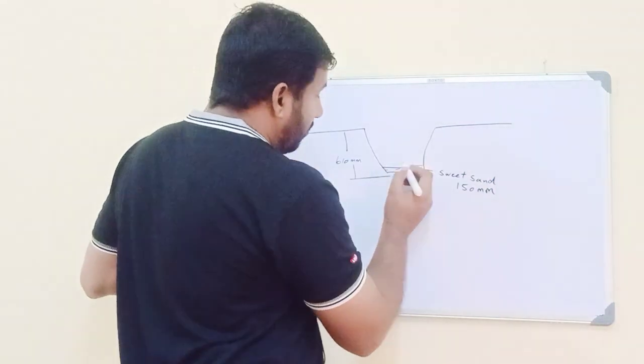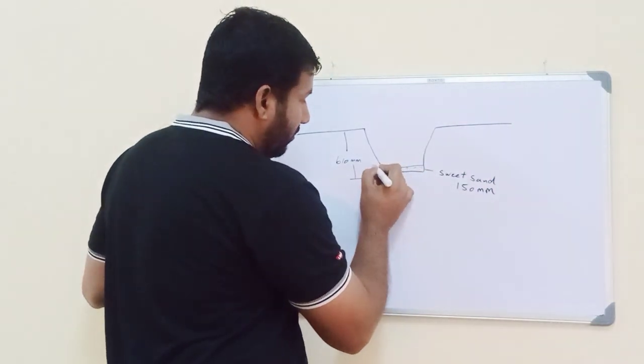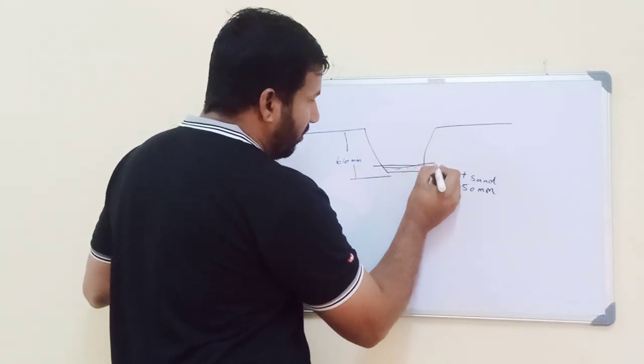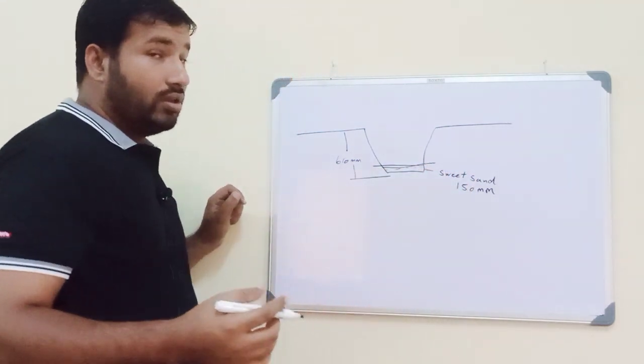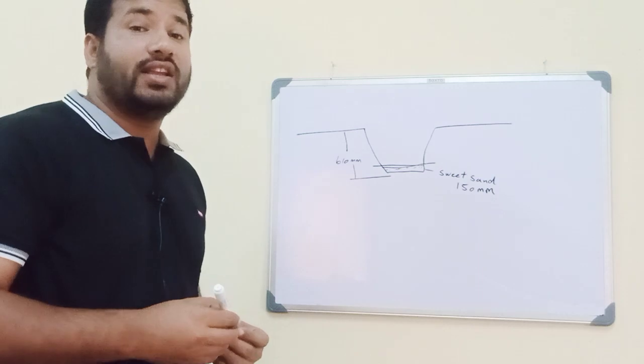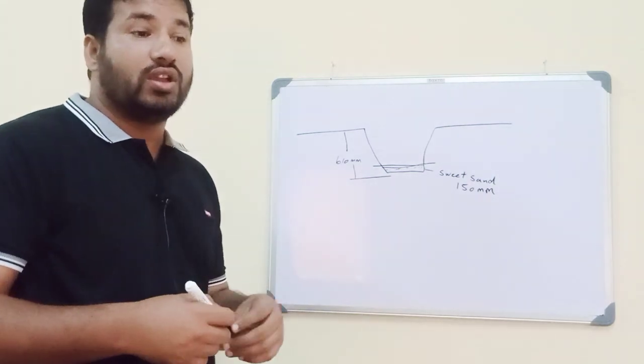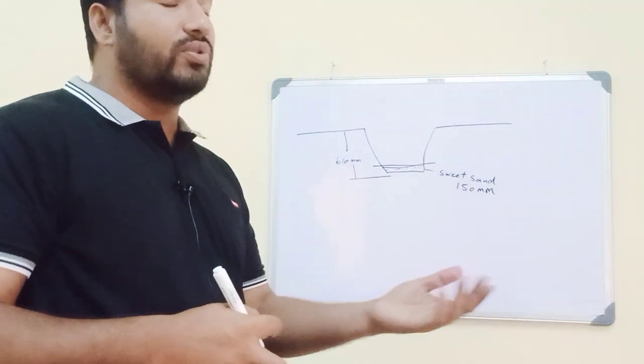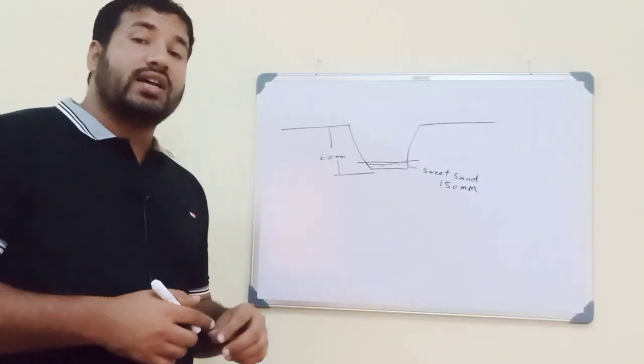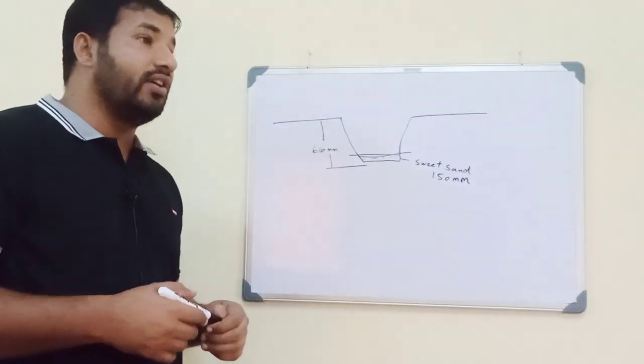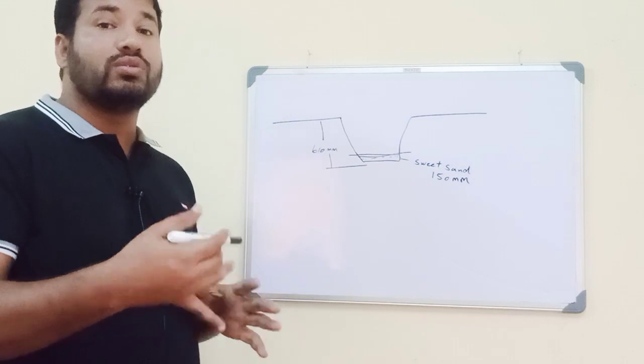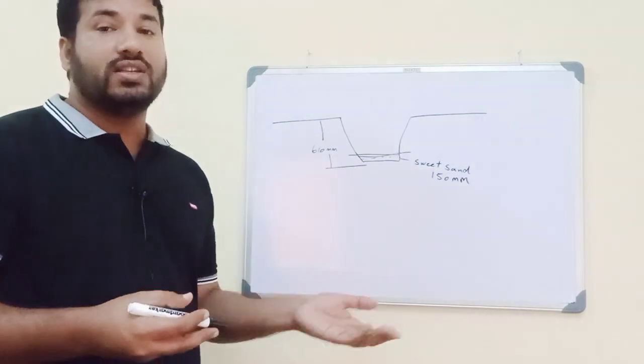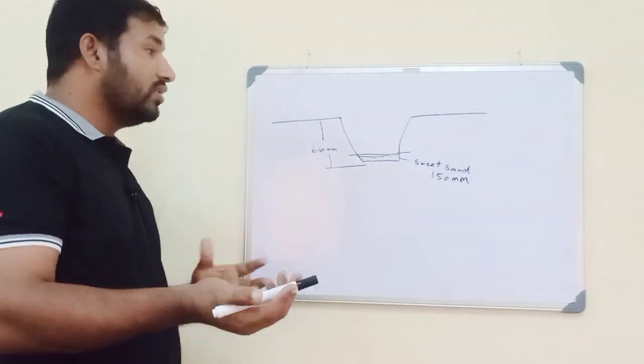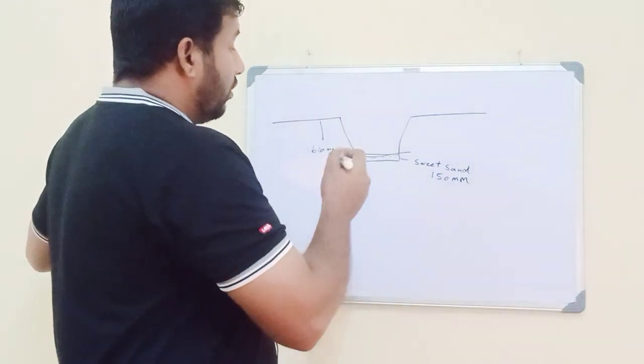Okay, now we will pull the cable. This is our direct buried cable. Direct buried cable should be armored cable, or sometimes they ask the question - if there is no armored cable and we want to pull it direct buried, some cables have written on the insulation that this cable is suitable for direct burial, even if it's not armored. So that one is okay.